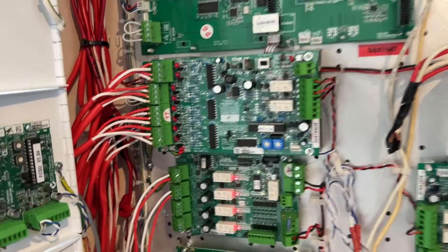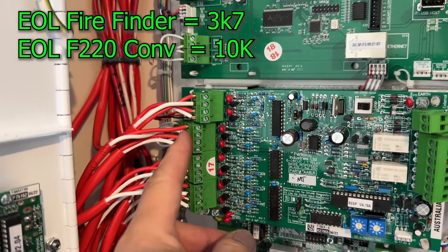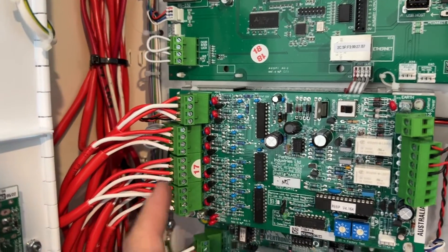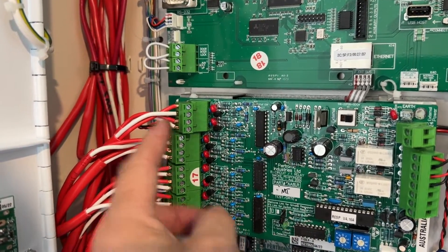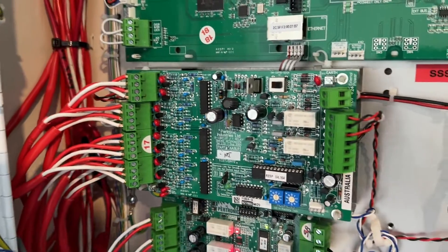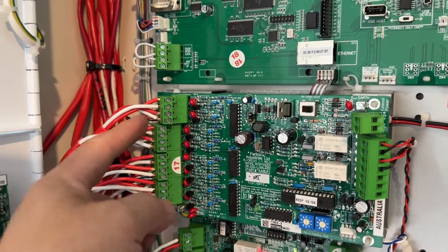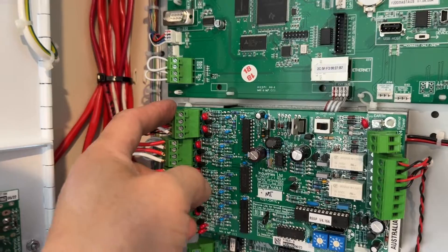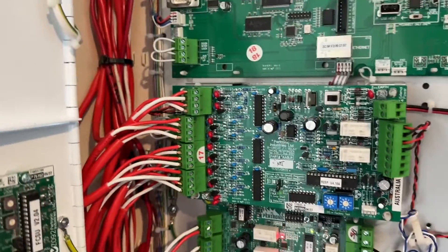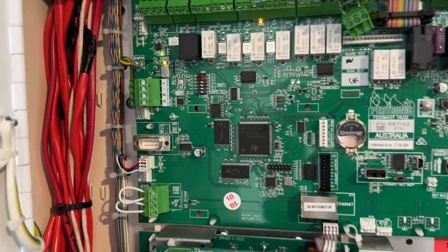For the end of line resistor of the Pertronic conventional module it's 10k. The old Ampak is 3k, or 3.2k. We changed all the end of line resistors to match what is required, and we were able to find all of them because there's only one detector per zone in this building — level one, level two, level three up to level eleven. So that is a bonus — one detector every level.